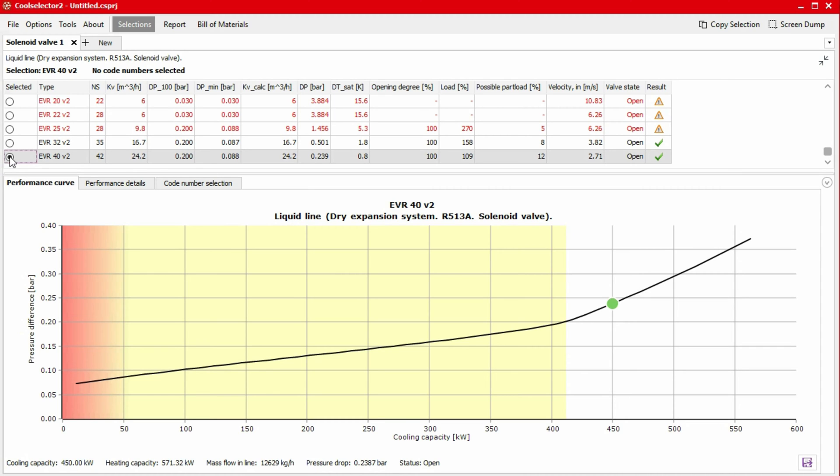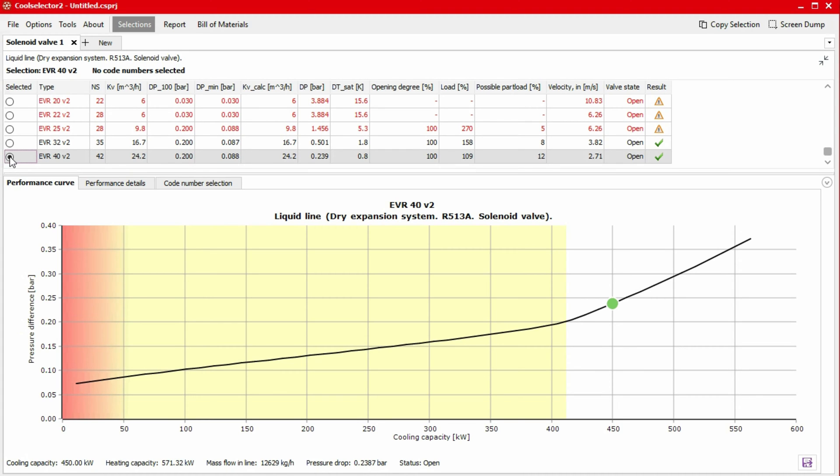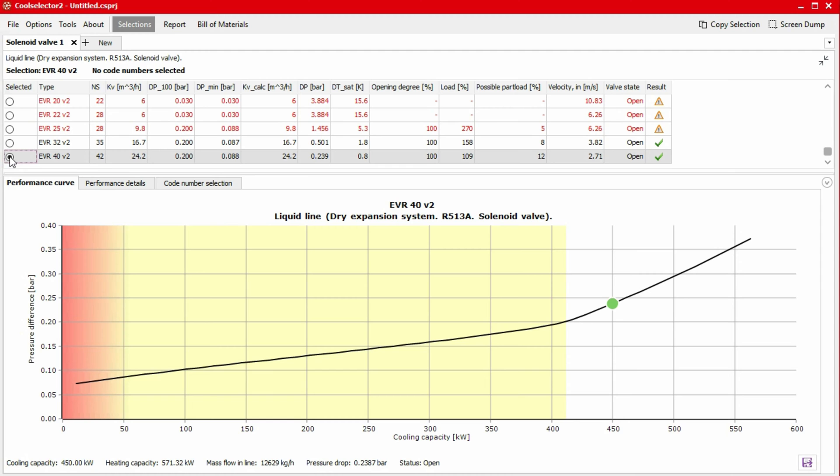A servo-piston-operated valve requires a minimum pressure drop to open initially, and then as the pressure drop rises, it starts opening further until it reaches a pressure drop which can open the valve completely. It is usually no problem to run in the yellow area where the valve is partially open, but we should consider this for our selection.